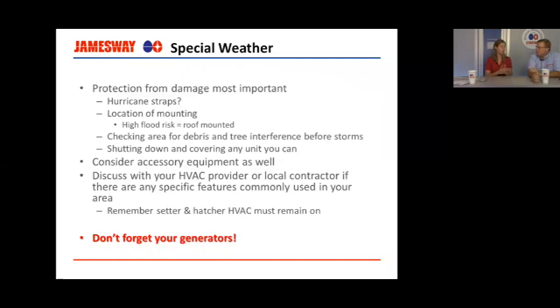And if your air handler hasn't been sized to take care of that extra air that you may need, that's going to be another problem. At the same time, in my work with 100% fresh air, I found that unless you're using chilled water and hot water coils, your temperature control is not as great as we can do with recirculation. And then also your pressure control can be not as great. So those are some other considerations as far as why you would not use it. That being said, Jamesway can and does provide solutions either way. If you like 100% fresh air, we understand the need for that. If you prefer recirculated air, we understand the needs for that.